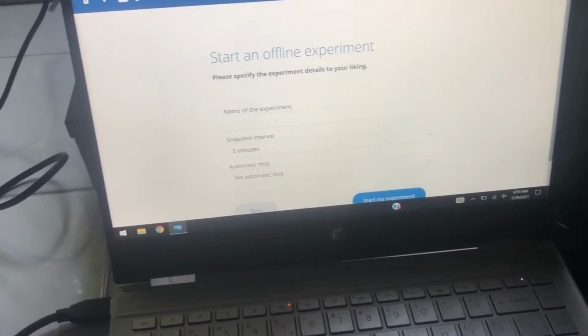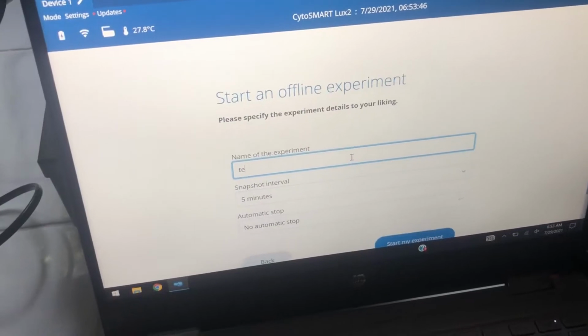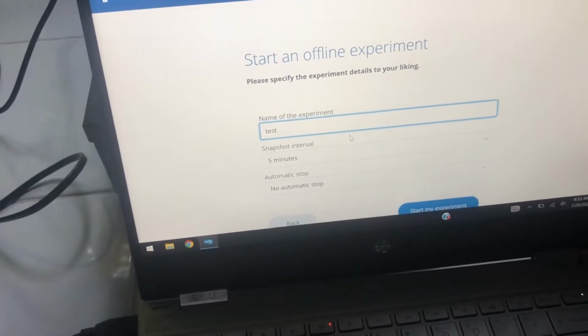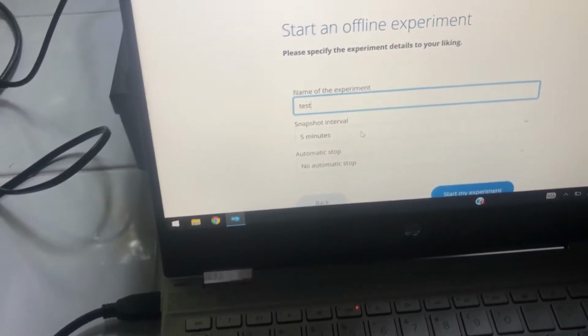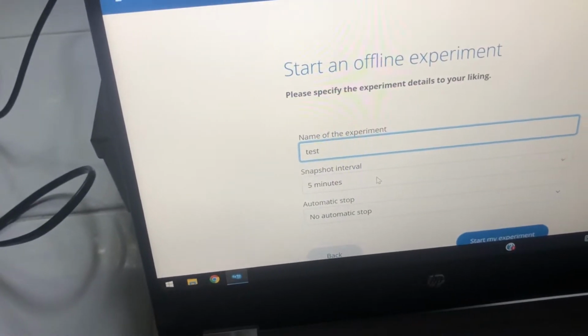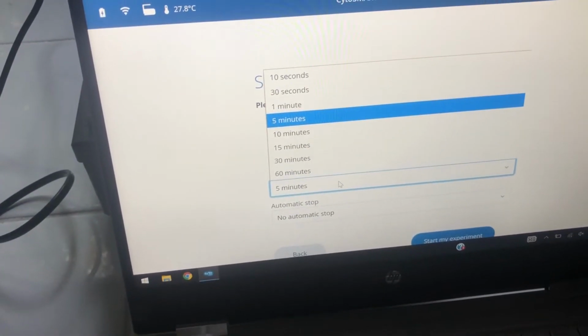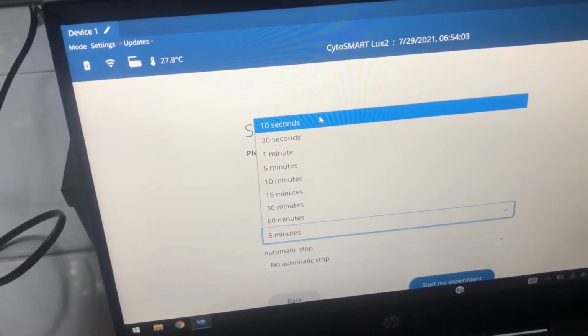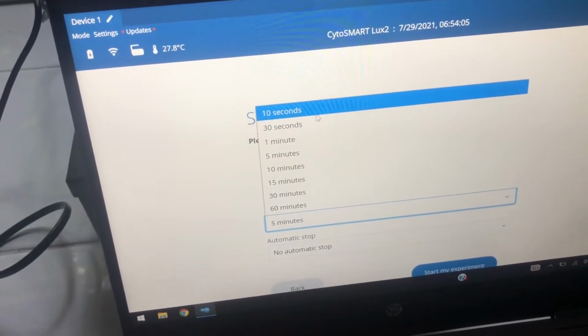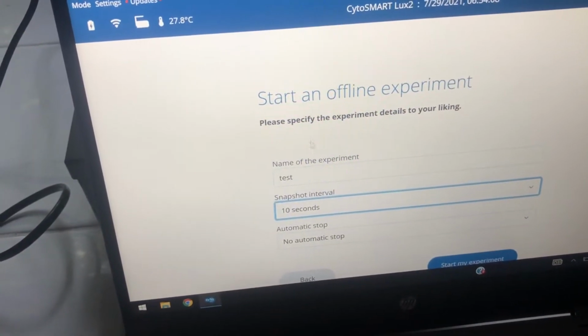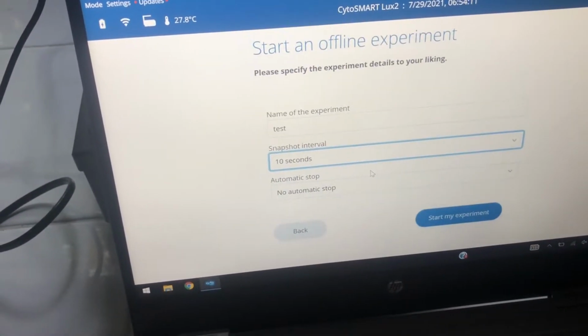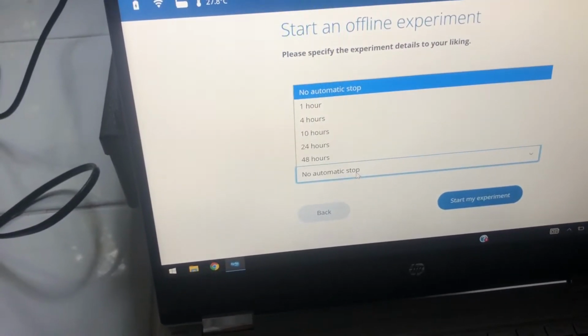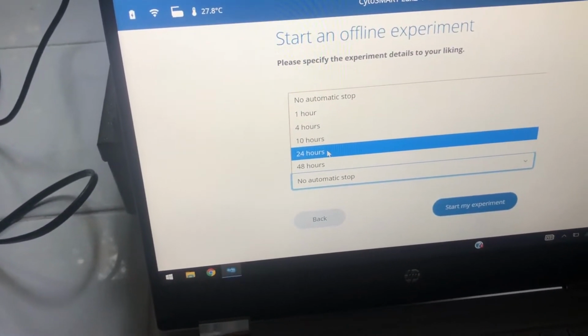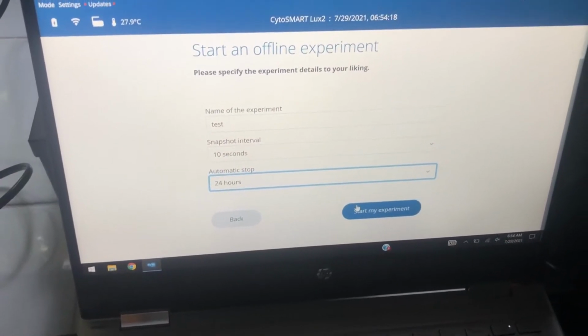And also you can start an offline experiment. Let's just start an experiment. I'm gonna give it a name. Let's just say test. And because it's live cell imaging, it's gonna require a snapshot interval. So what happens is the microscope is gonna take a snapshot at a predefined interval. So you can do from 10 seconds to 60 minutes. So once I go to 10 seconds, I can even ask it to stop like in 24 hours. Then I'm gonna start my experiment.